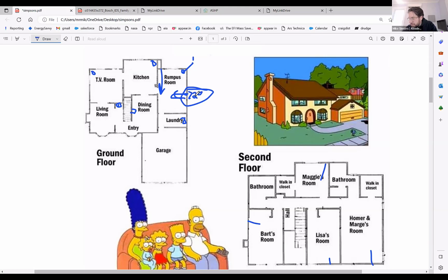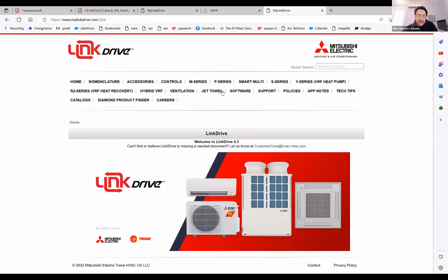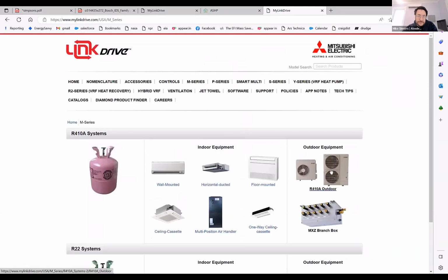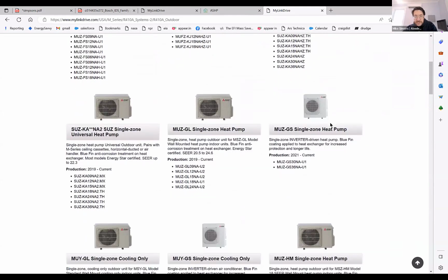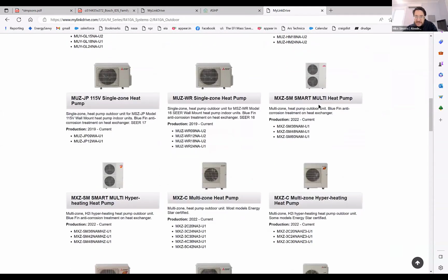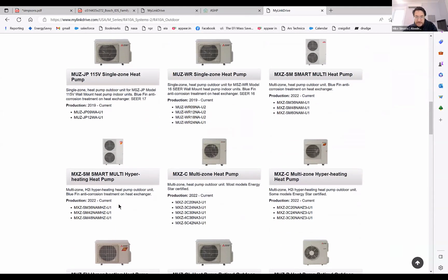Your load is 32,000 for heating and 25,000 for cooling. So if I'm thinking about this, let's go over here. I'm looking at Mitsubishi's equipment. I'll see that they have multi-zone hyperheat heat pumps, and they have some that are 20,000 BTUs, 24, 30, 36, 42, 48. So with the load being 32, I would take a look at the 30 as well as the 36 and see which one has better performance.